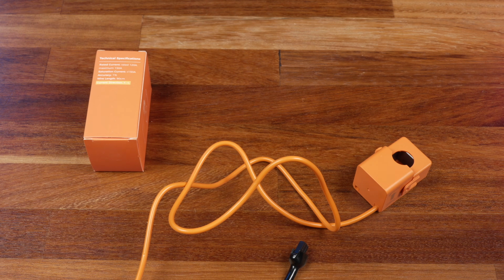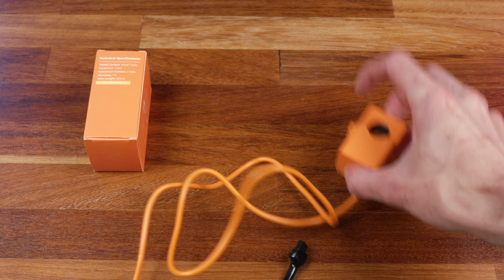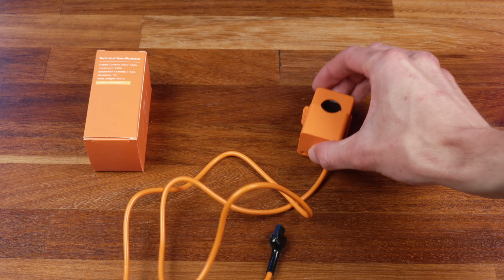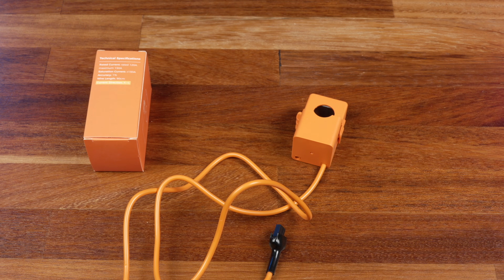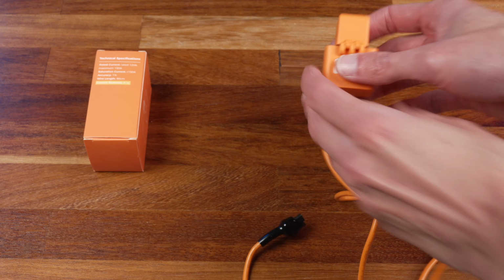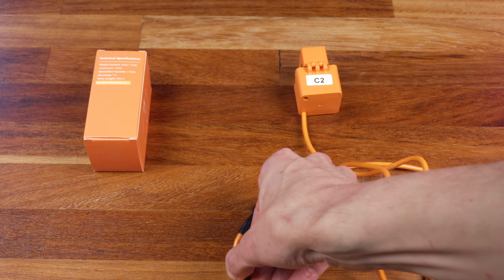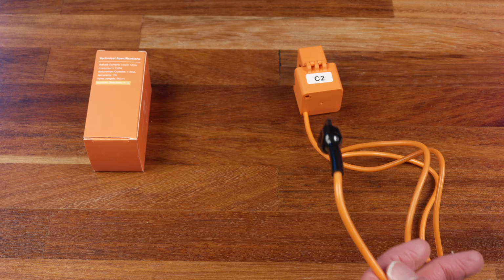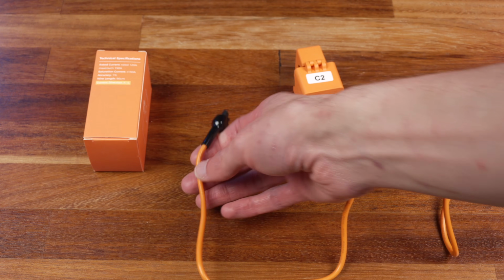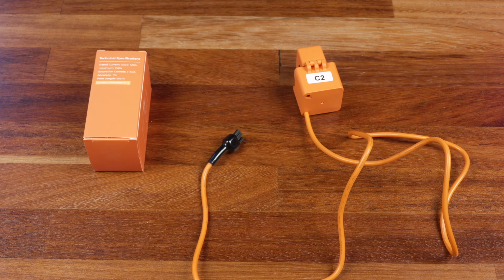Now the final thing that's worth bearing in mind with these CTs is what I suspect these are, what are known as unburdened current output CTs. The way these work is that, well, they're a transformer. You pass a current through a wire that's passed through the core here, and then the CT will present a current that's proportional but smaller to the current passing through it on its output. The other type you can get are voltage output CTs, where they produce a voltage on their output that's proportional to the current that's passing through it.